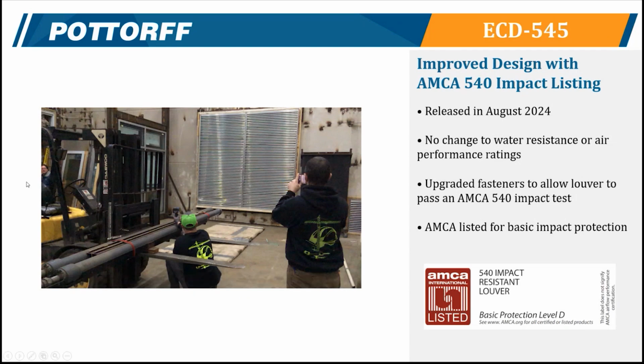Also in August last year, we made a product improvement, not a new product. We've had our ECD 545, a 5-inch wind-driven rain louver, in our catalog for a long time, and we added AMCA 540 impact resistance listing. It really wasn't a visual change—if you compared new to old versions you wouldn't know the difference. Primarily we upgraded the fasteners between the parts so everything stays connected when hit with a 2x4. This didn't affect the water resistance or air performance ratings, and we kept the same profiles—it just added that impact protection as something extra.